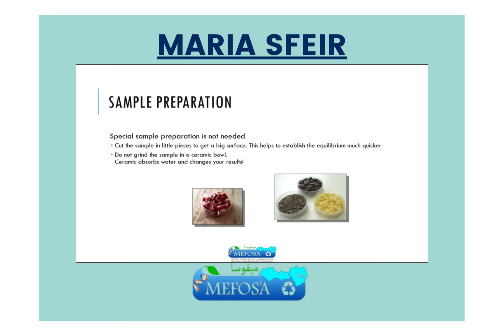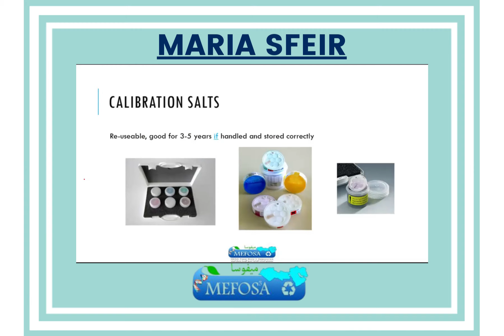Regarding the calibration, we have calibration salts. They are reusable. They can last between 2 and 5 years if handled correctly. This is an advantage because at other companies, the calibration salts are single-use.